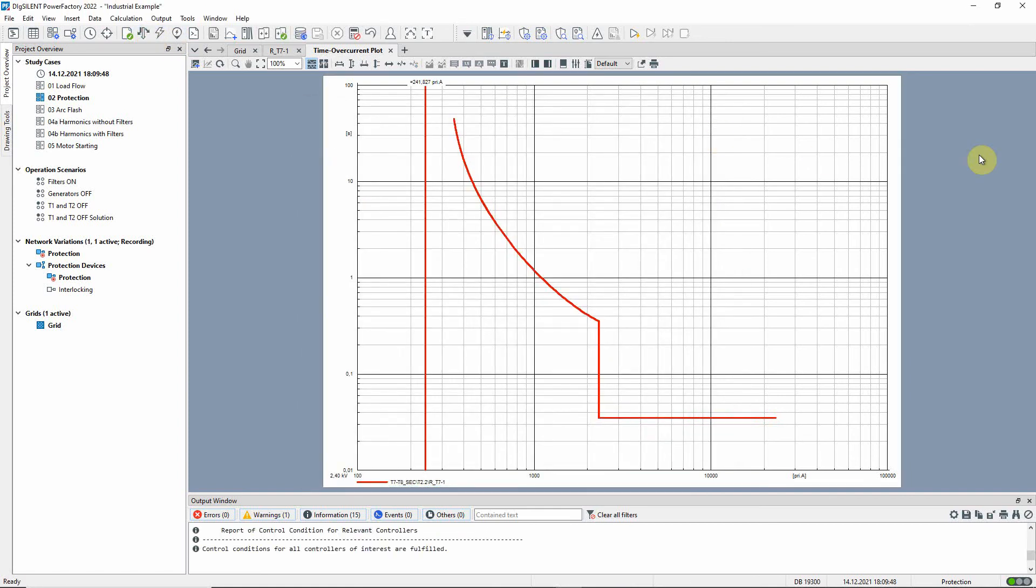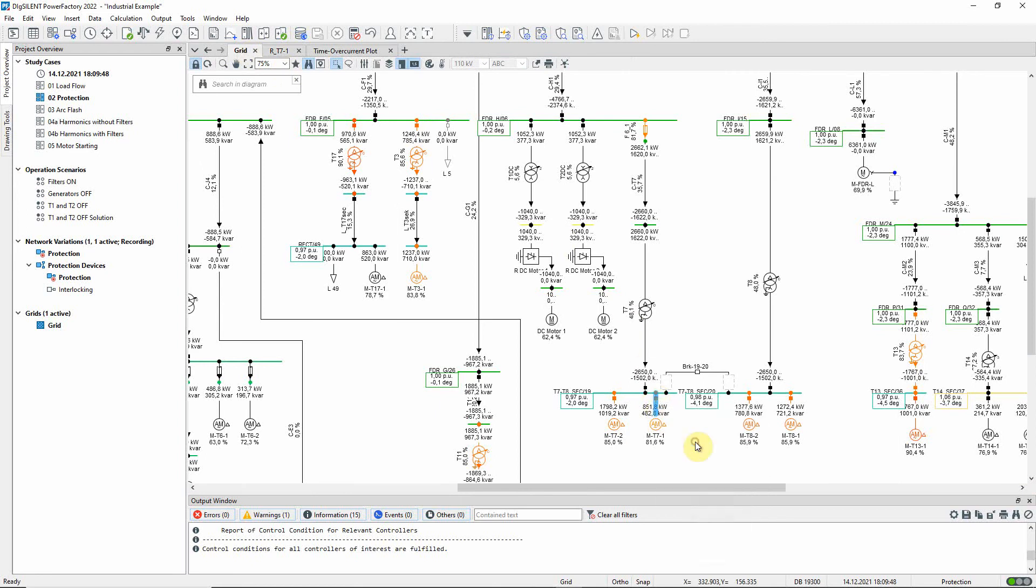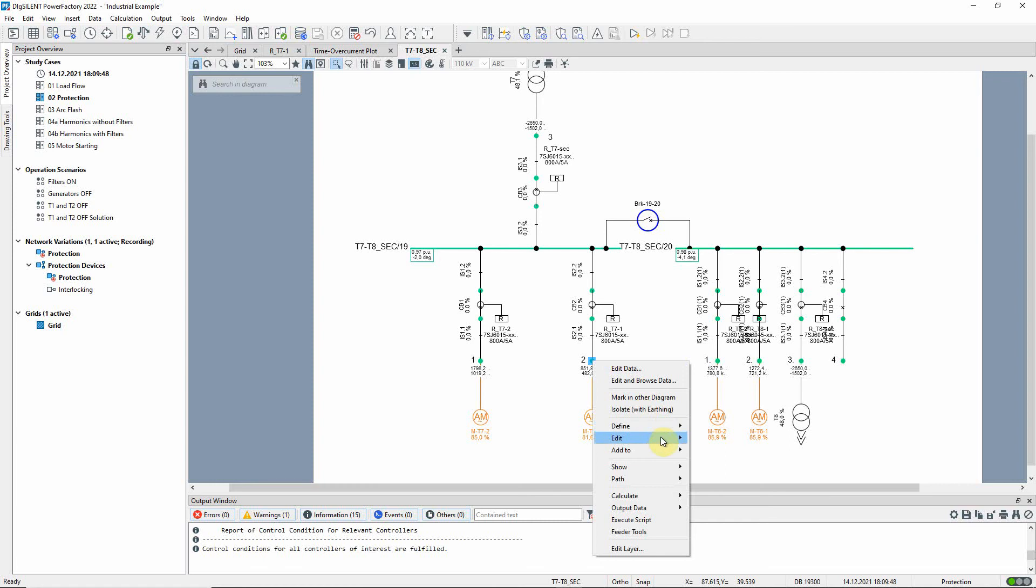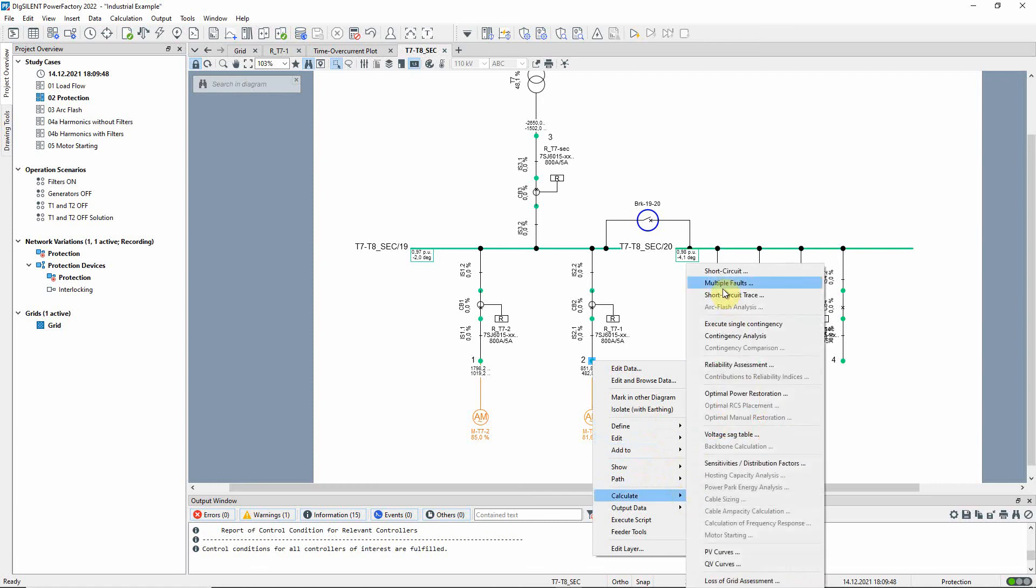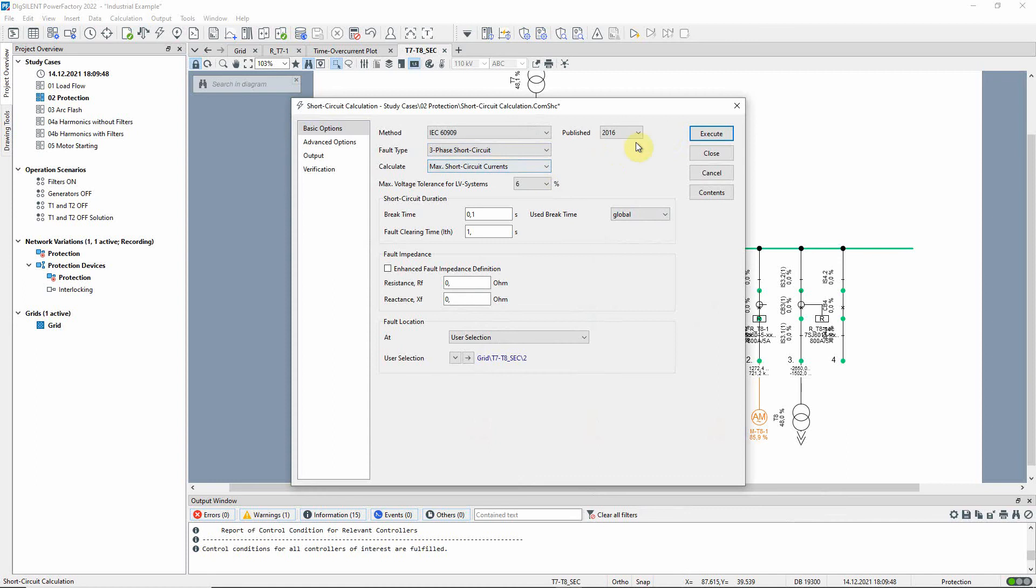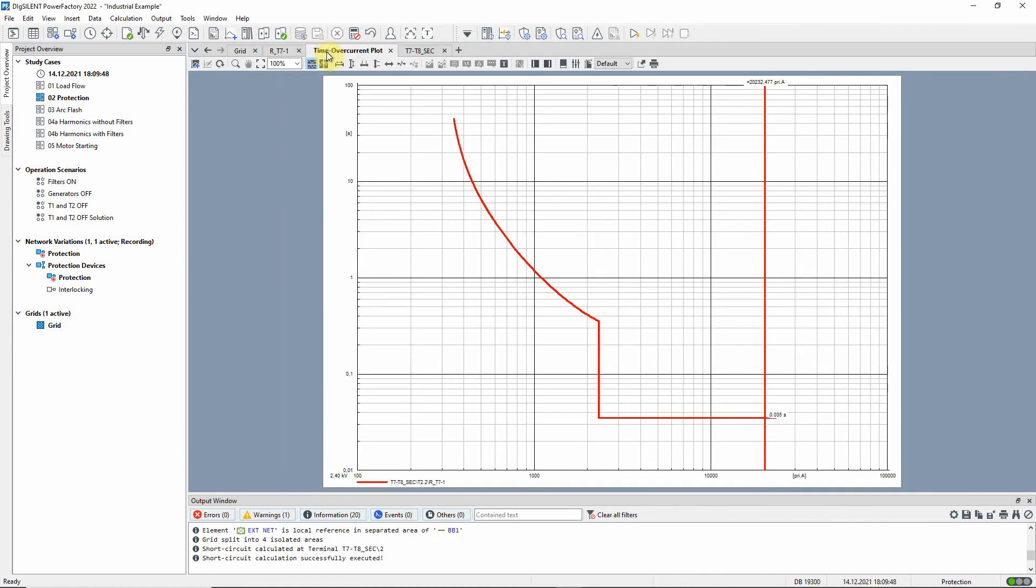The new line on the diagram represents the current seen by the relay. We can see that it is below the curve and so the relay will not operate. Now let us run a short circuit calculation for a three-phase fault at the connection point of the asynchronous machine. We can see that for this fault the relay will trip instantaneously.